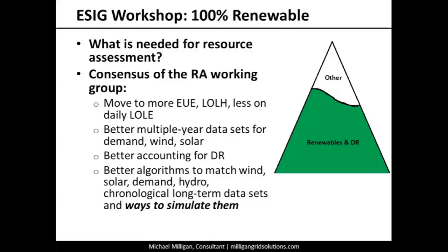Sure. What we typically want to do, so this is kind of historical, we say, well, our peak demand is going to be 10,000 megawatts, and so the resource adequacy question is how many megawatts do I need to build? And we need to build more than what we're going to have. And that does get to the issue of planning reserve margin. I think having a planning reserve margin is great. What I really don't like is the idea that if you're at 13% or 15% planning reserve margin, you're okay.